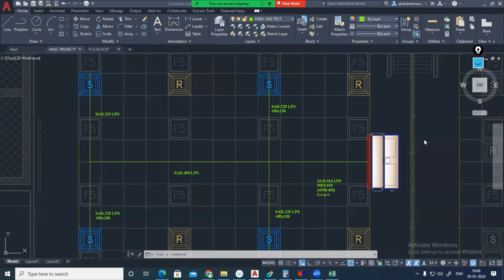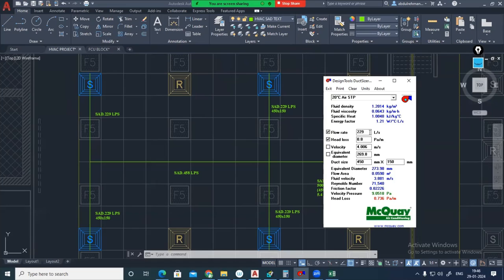First, I need to find the flexible duct diameter. The flexible duct diameter you can size using this one, no problem. But the absolute roughness value of flexible duct is different. When we are calculating the ESP, this value has to be considered. Accordingly, the fan has to be selected. That's the only problem.